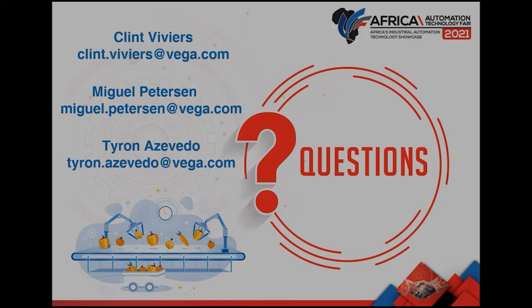And then I'll answer this question. The question is, how can we measure open channel flow? This measurement is done with two of our units: a non-contact radar level device coupled with one of our controllers that does the calculations for us. So we'd use a non-contact device into a V-notch weir, rectangular weir, or Venturi type setup. We have all these calibration options available on our device, so depending on what open channel you have, you make those selections and the device is calibrated that way. Coupled with a signal conditioning controller, we're also able to have a totalizer function, where we can totalize the flow through these open channel flows. So short answer, yes, it can be done, quite simply with a level transmitter and a controller.